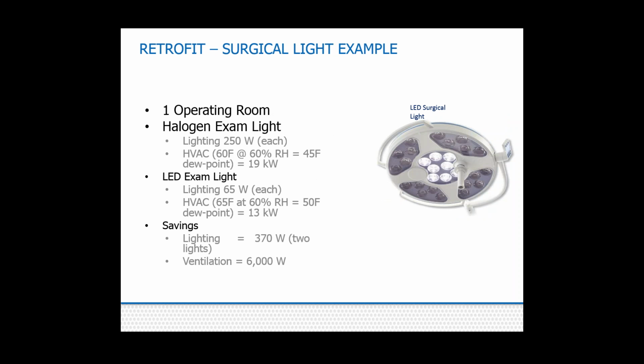And here I just did a quick calculation of an operating room with 2 surgical lights being retrofitted to LED instead of quartz halogen. And we're showing in the end a savings of about 370 watts by changing to LEDs. But if the people using the operating room set the thermostat up, we've got 6,000 watts of HVAC savings from overcooling, having to overcool that air going into the space. So it can be a big deal, and especially for the facility that's having trouble, like the surgeons keep asking for it colder and you start missing that 60%, it can be a big deal for you.